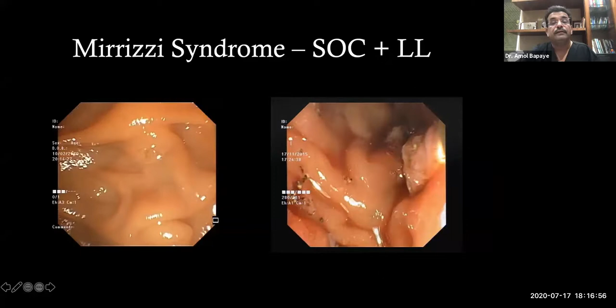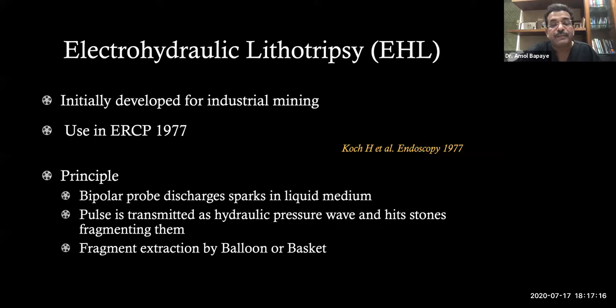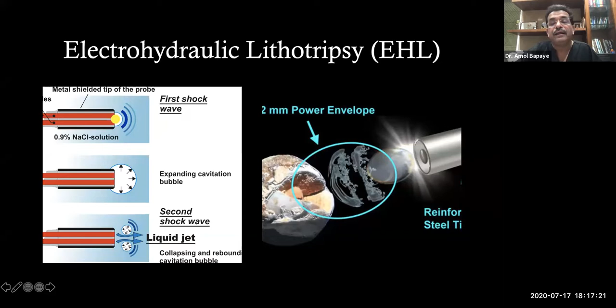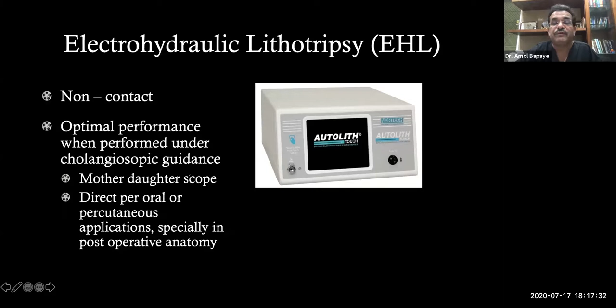Instead of laser, electrohydraulic lithotripsy can also be used. It was used first in ERCP in 1977. The principle is a bipolar probe discharge which sparks in the liquid medium, and this pulse is transmitted as a hydraulic pressure wave and hits the stone to fragment the stones. And this is how it looks. So you have a bubble forming, and then that hits the stone and causes fragmentation. This again is a non-contact technique, and the performance is optimal when it is performed under cholangioscopic guidance.